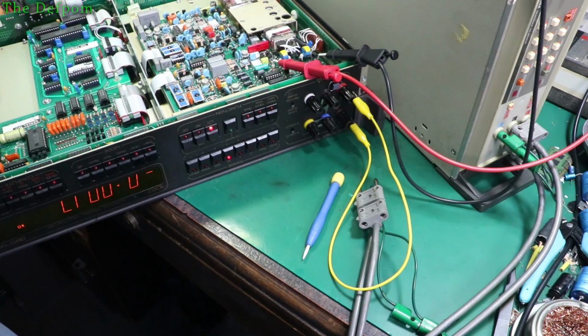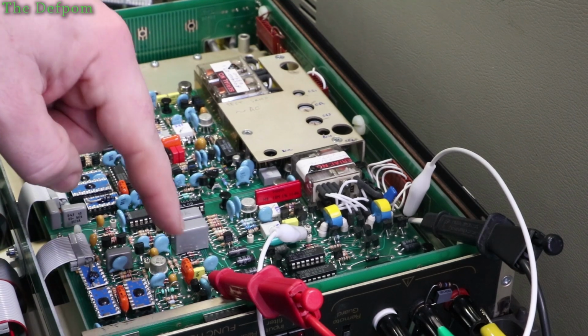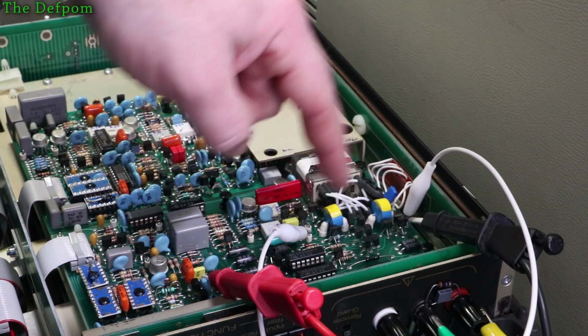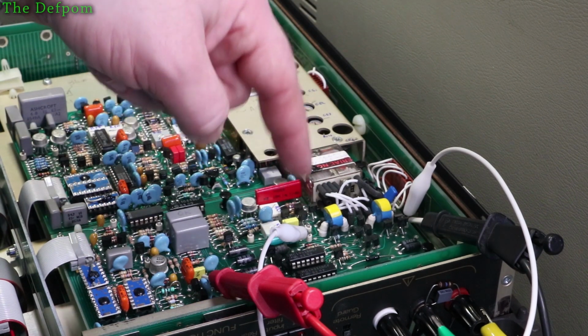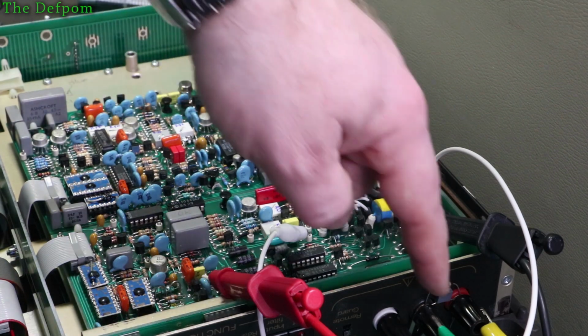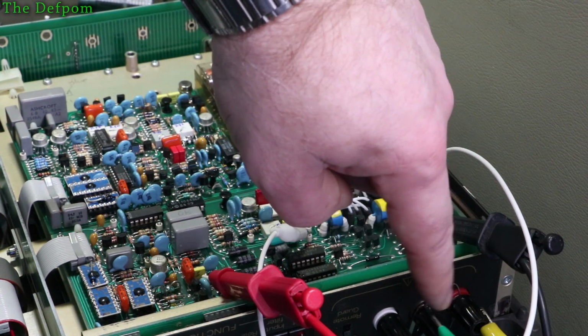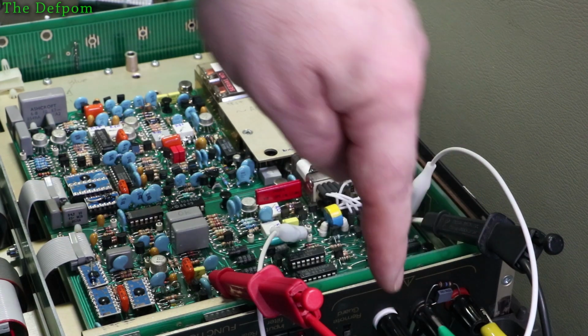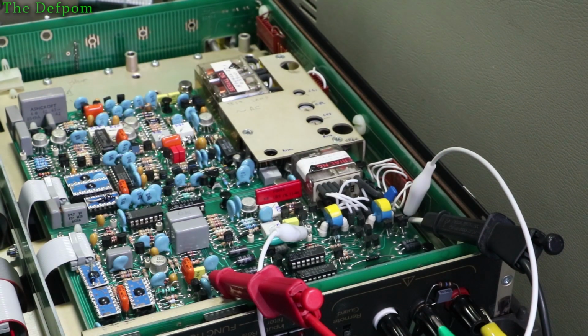I'll have to do more work on that part. There are some more steps. The next thing I have to do is hook up onto TP13 over here and link TP1 and TP3 together. It didn't say anything about changing this. I also mentioned linking the low to the ohms guard, which I've done with a jumper link. It says it has to be 0 plus or minus 50 microvolts. That's fine, we're getting about minus 30 microvolts. So it's within spec.